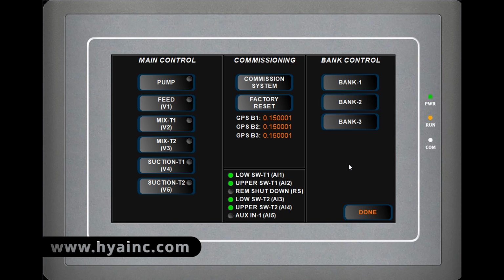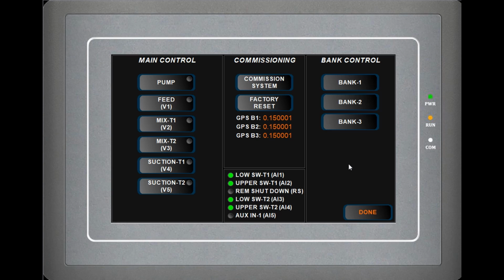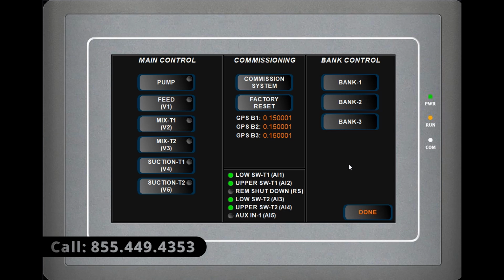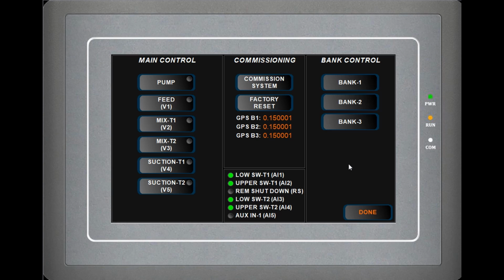This was a pretty short tutorial, but it's super important to go through those steps when you first plumb in the system. You do not want to find out that you have a plumbing problem, a leak, or whatever, in the middle of an auto commissioning process — you'd have to cancel the process, and it gets kind of funky. So do yourself a favor and go through this process, and be sure that the valves are all working like you'd expect, and that the volume feedback is coming in as you would expect.